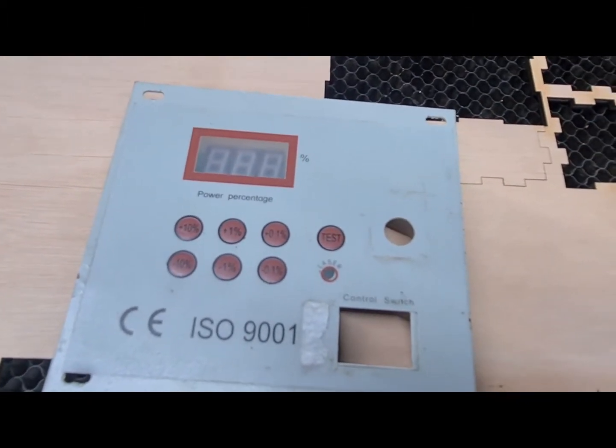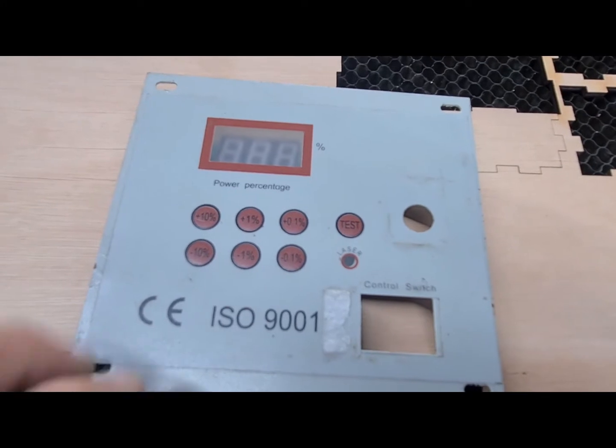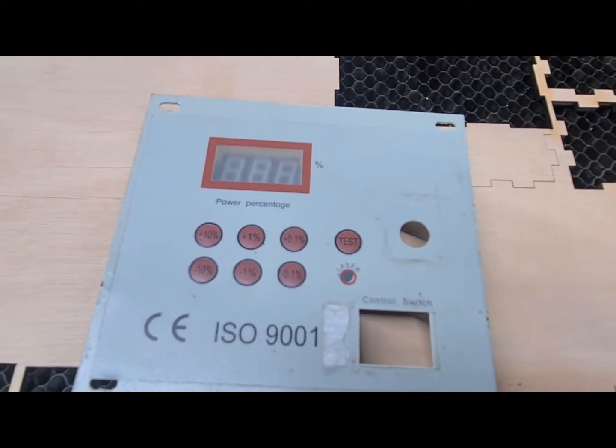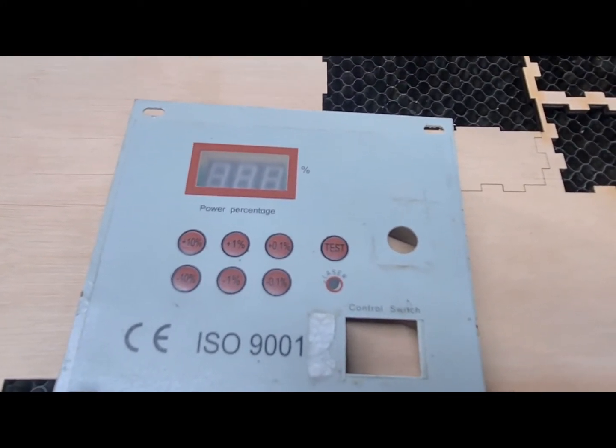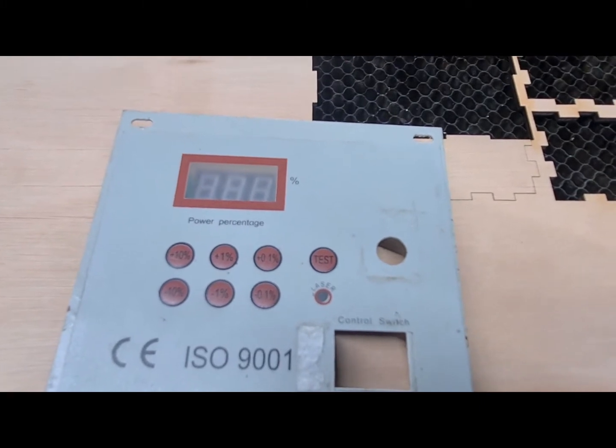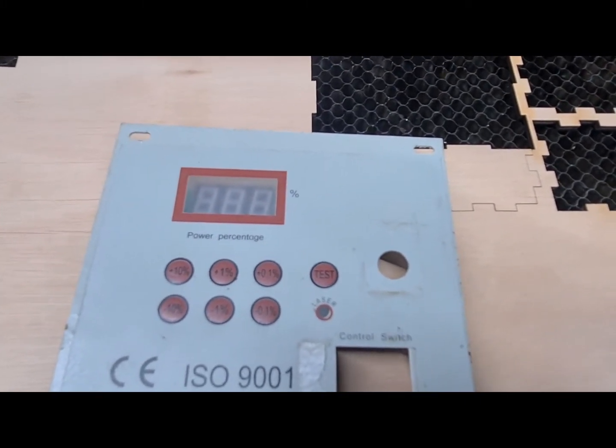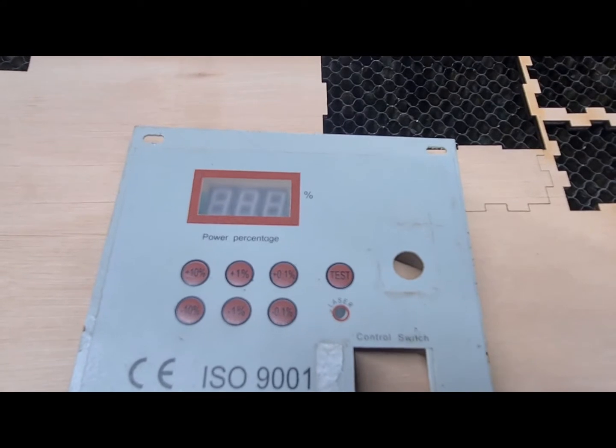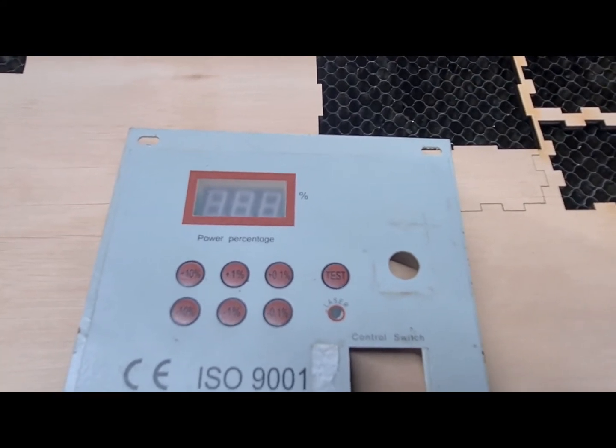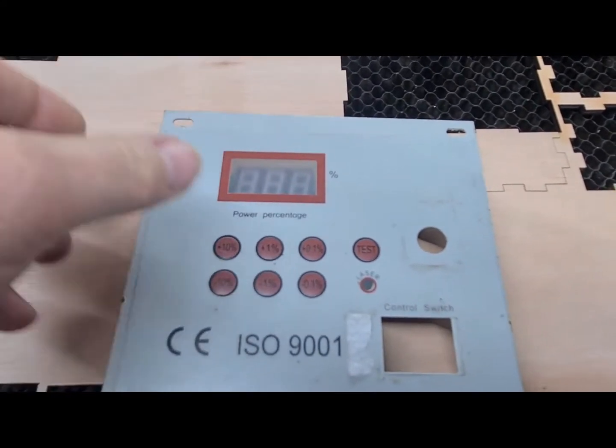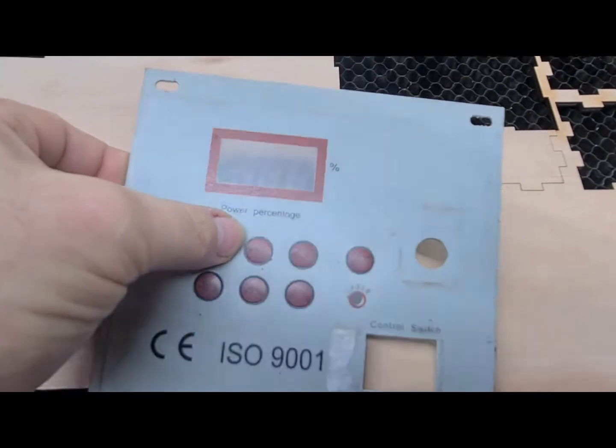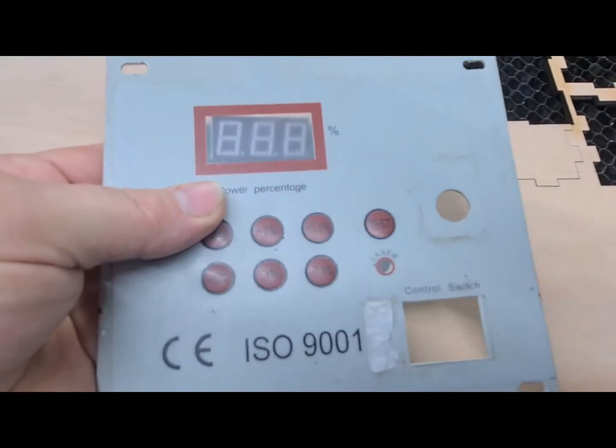It's shit. It's not even close. If you run a multimeter on it, you set it at 50%. In theory, at the power supply, which I'll show you in a minute, that should read 2.5 volts. You've got 0 to 5 volts, 0 being 0%, 5 volts being 100%, therefore 2.5 volts should be 50%. Nope, not even close. That reads 30% on here, 32% I think I measured it at.